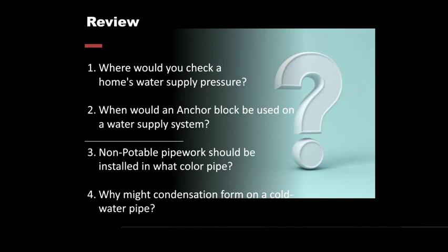And it's requiring anchor blocks, big concrete blocks, at changes of direction, under fire hydrants, things like that, to hold it all together. It's totally reliant on those anchor blocks from preventing the internal forces when you get to like a change of direction, blowing the thing apart. So that's when it would be used. Obviously, there's a reason why people keep getting it wrong. Maybe something in the study guide, I didn't get to that level of detail.